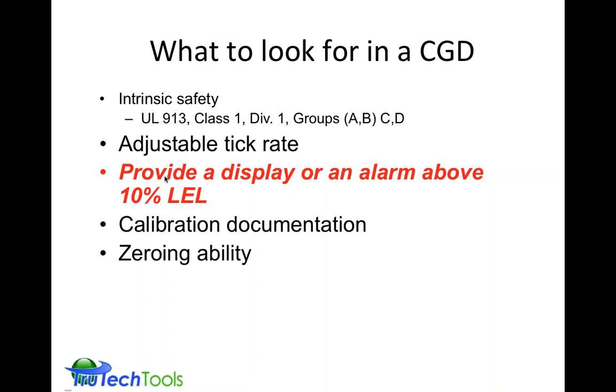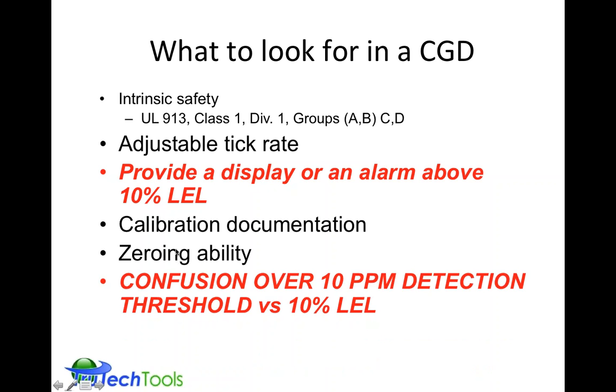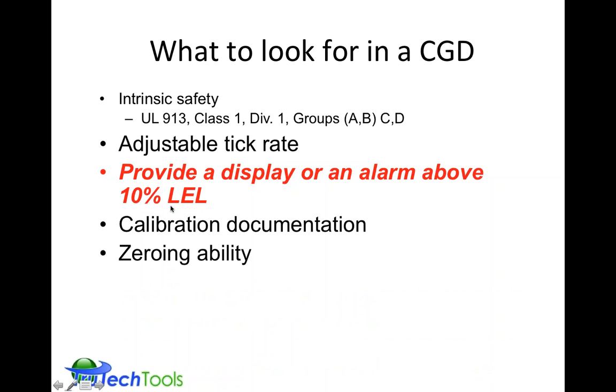Documentation of calibration is essential. Zeroing ability is also something that can be done by a lot of meters. So really it boils down to providing the display or an alarm above 10% LEL, which rules it down to just a few detectors that are compatible with the standard.